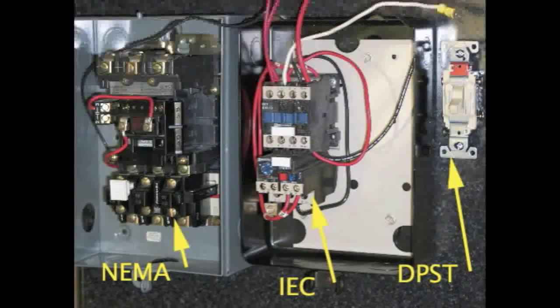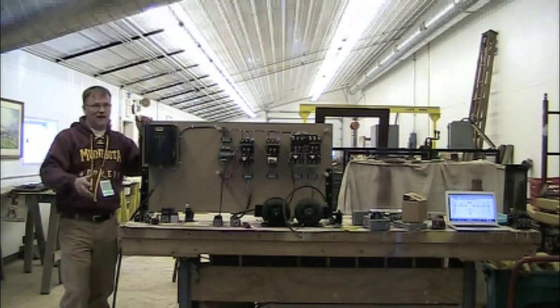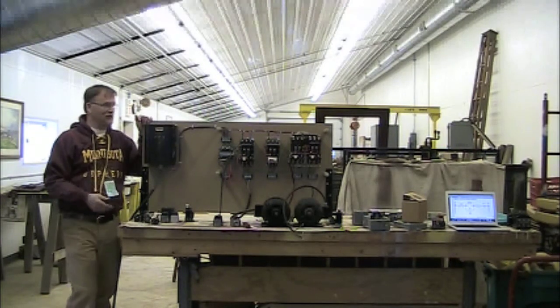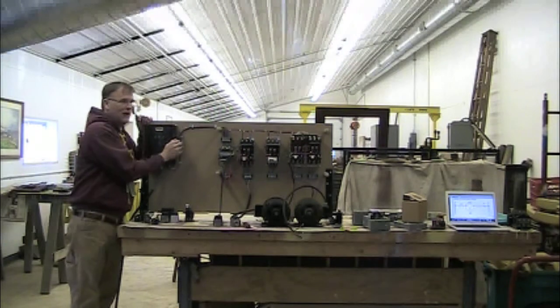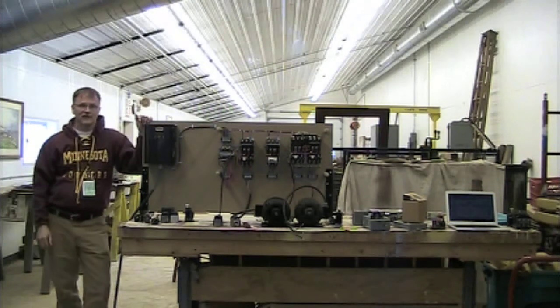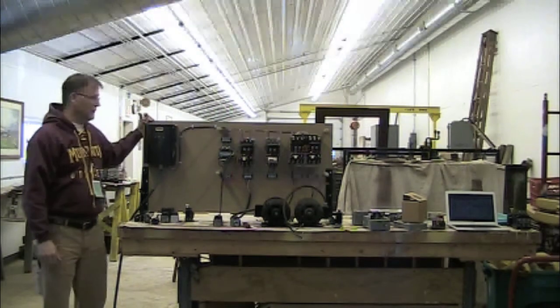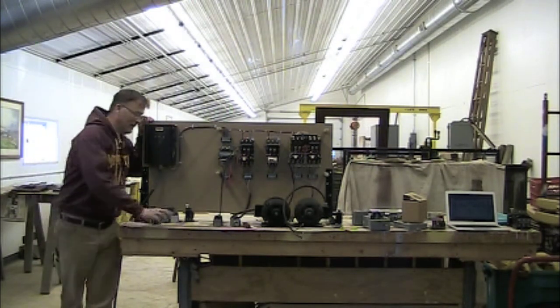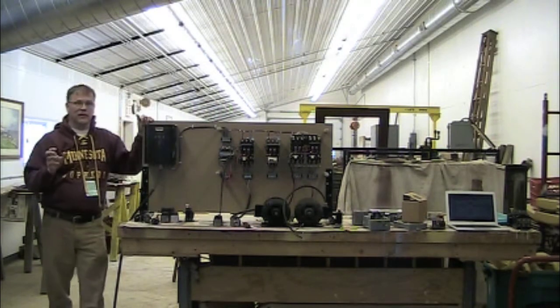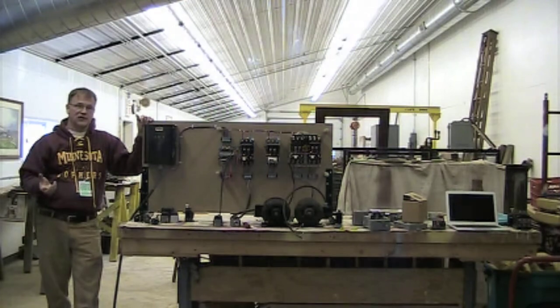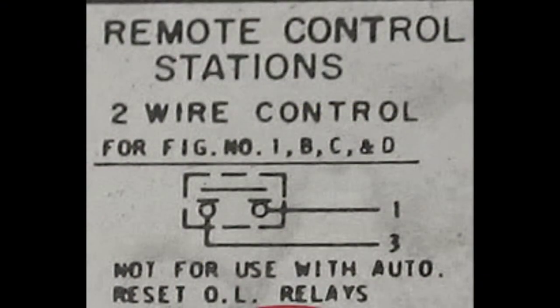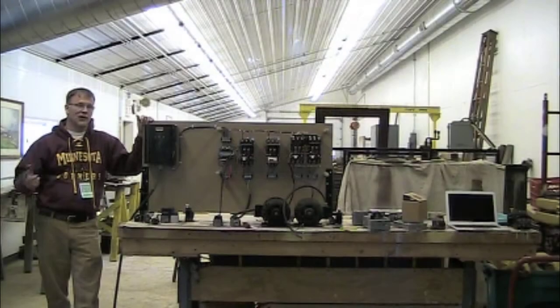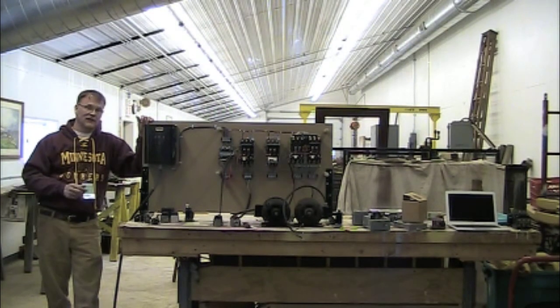Right. So the one thing that 3-wire control gives you, and this is preferable on most machinery, is under voltage release. So if I drop the power and turn it back on, that device is not going to start. The other side of it is what's called 2-wire control. That's where you don't have a start button, but some kind of input device, like a float switch, a pressure switch on your air compressor, or a thermostat. It calls for pressure and just closes the contactor directly. So in that type of scenario, you don't have any under voltage release. When your power comes back on, if it's calling for pressure, it's going to start. So there are ways of provisioning things for that.